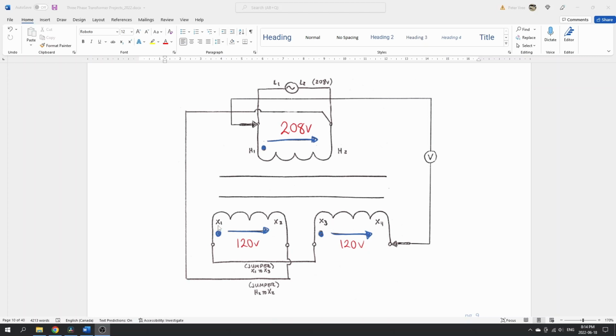And we're trying to determine the relative polarity. So you can see that on this diagram, I've put a dot on H1 and X1 and H1 and X3, saying that they have the same instantaneous polarity. So we're trying to determine which one is actually X1 and which one is actually X3. And so we're connecting up the primary and the secondary together. So in this diagram, I've got H2 going over to X2 right here. So I thought I had H2 going to X1, but in fact I've got it going to X2.